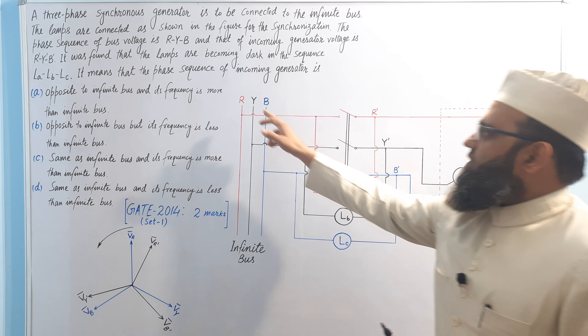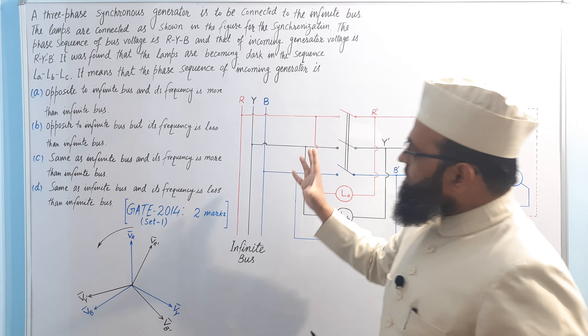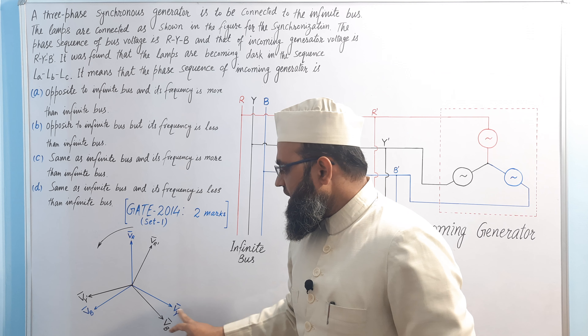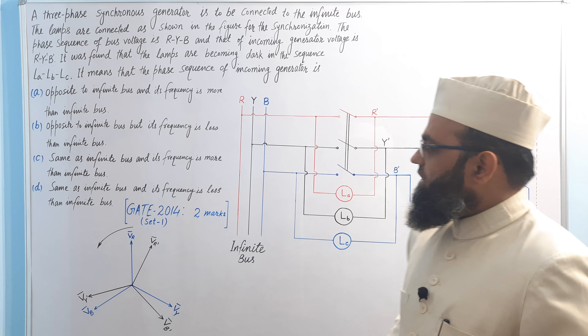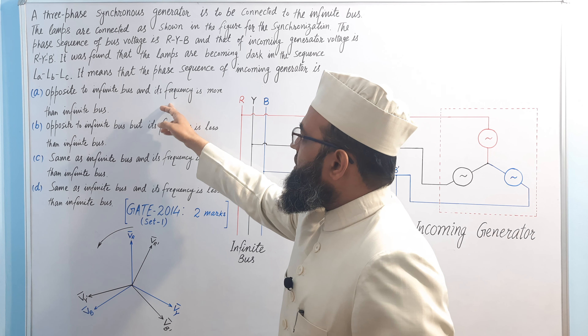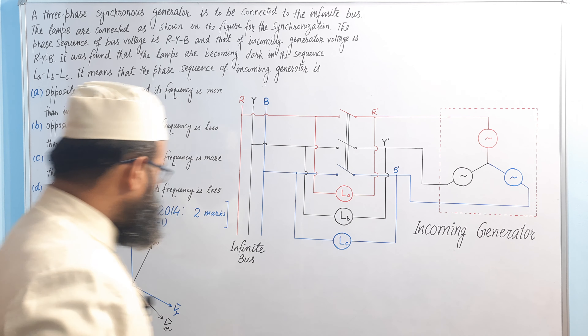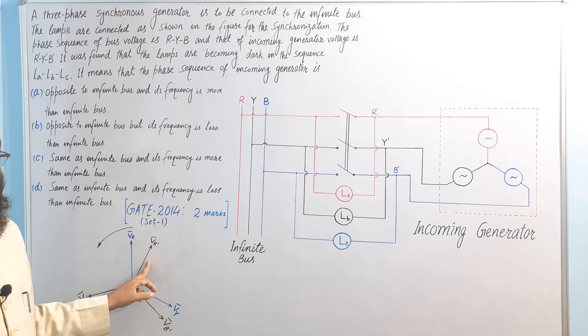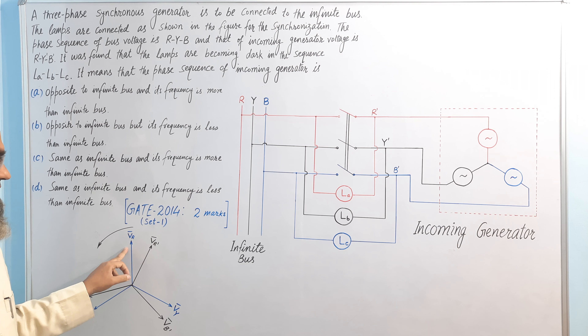The RYB representation has been used for the infinite bus, so the three phase voltages Vr, Vy, Vb are rotating in anti-clockwise direction. Let us assume option one is correct — that is, the frequency of the incoming generator is more than the infinite bus. In that case, this phasor will rotate at a higher frequency, so its speed of rotation will be higher.